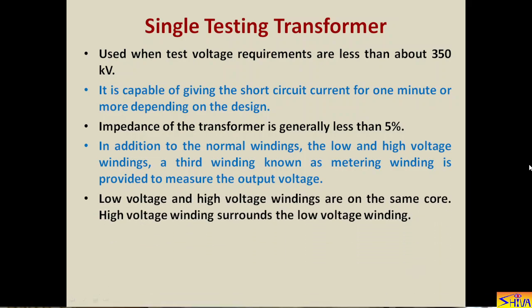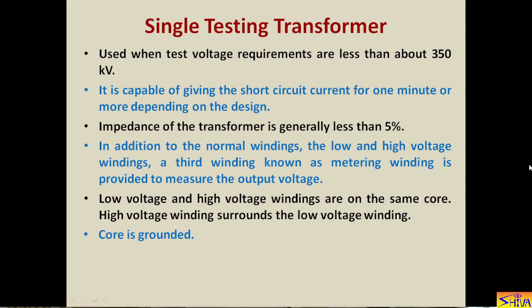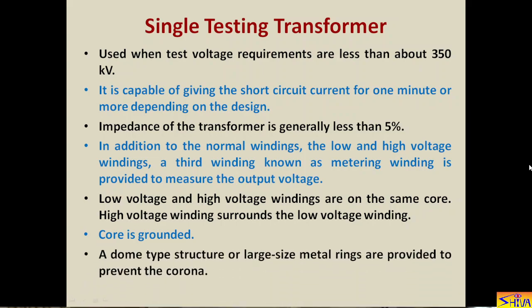The low voltage and high voltage windings are on the same core, with the high voltage winding surrounding the low voltage winding — I will show this by diagram. The core of this high voltage testing transformer is grounded — I will also show this with a diagram. Finally, a dome-type structure or large-size metal cap and metal rings are provided to prevent corona — this too will be explained with a diagram.